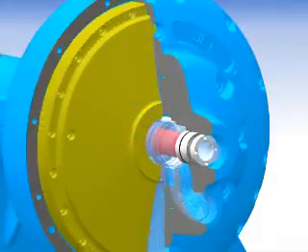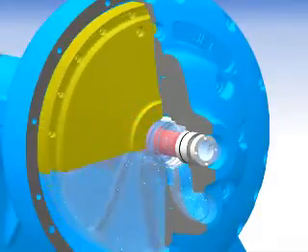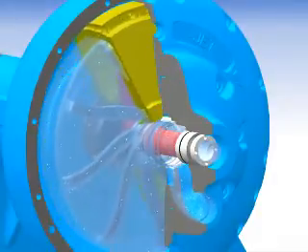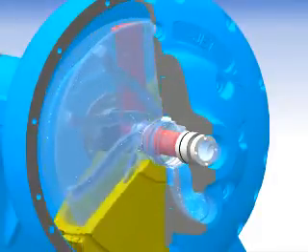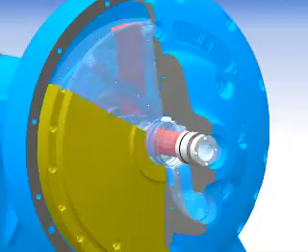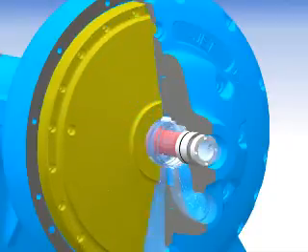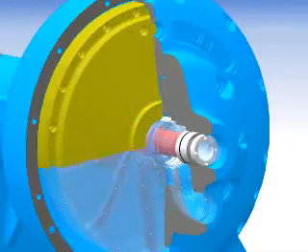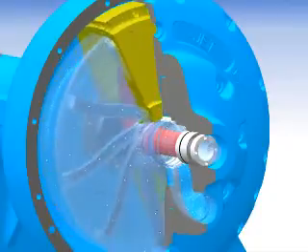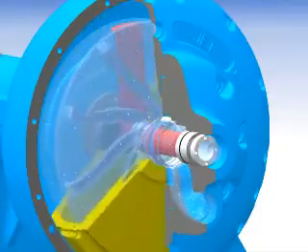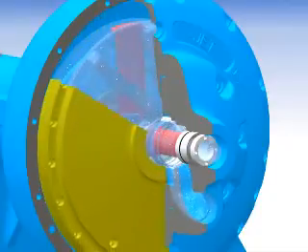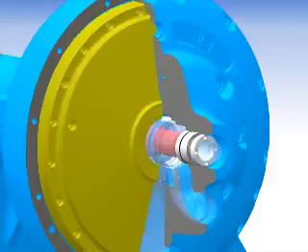The fluid is accelerated through the rotor vanes, generating approximately half of the overall outlet pressure of the pump. At this point, the fluid rotates at the same velocity as the rotor.